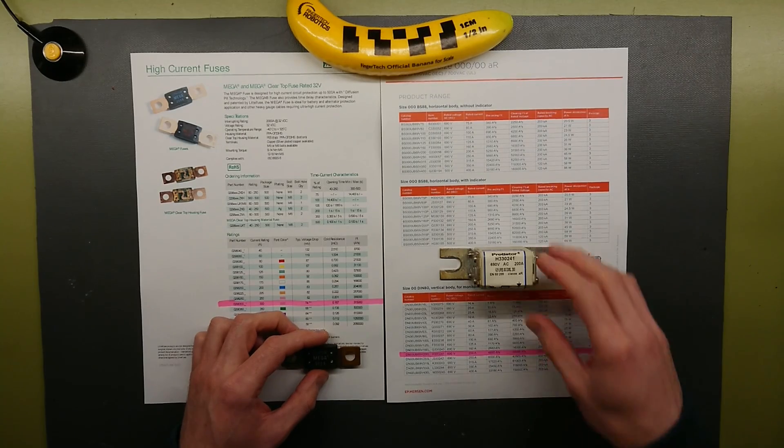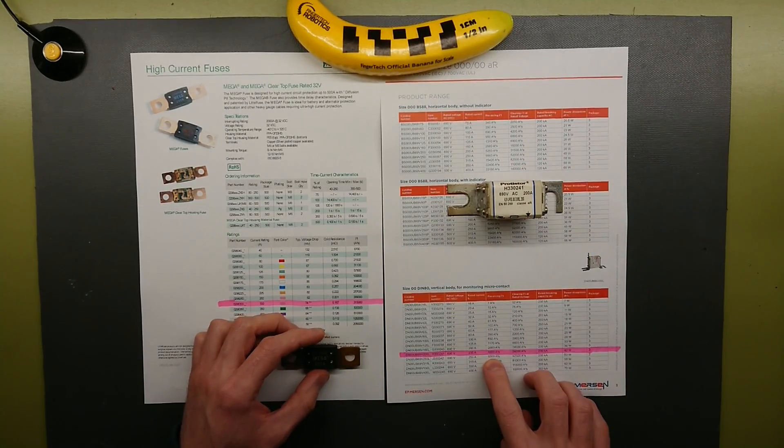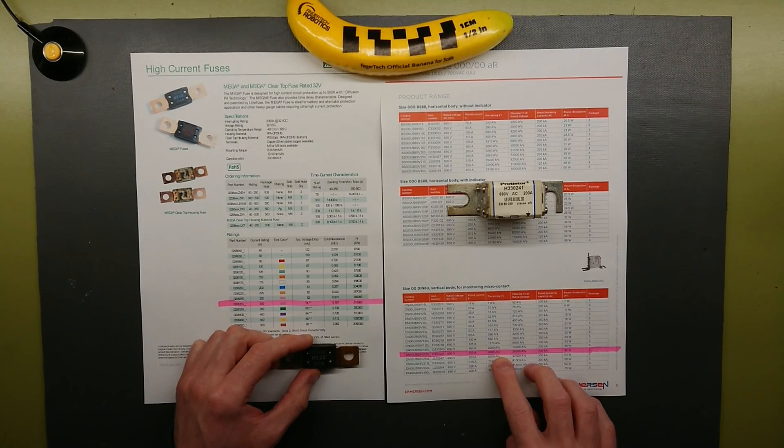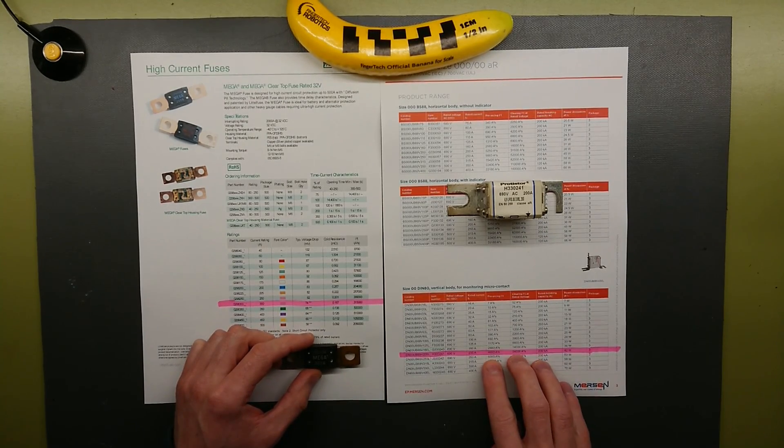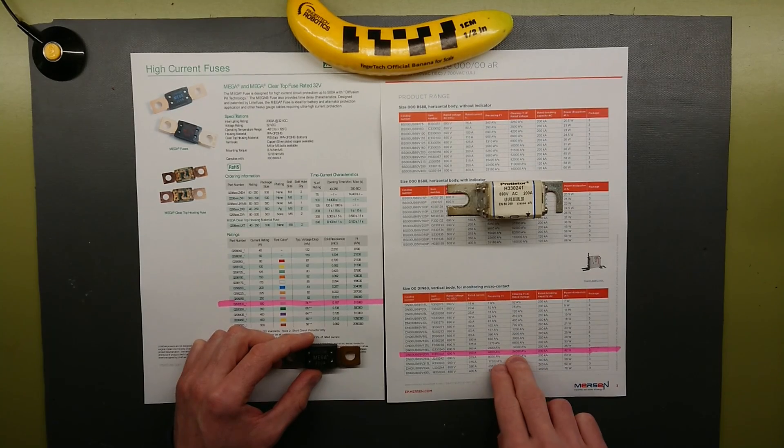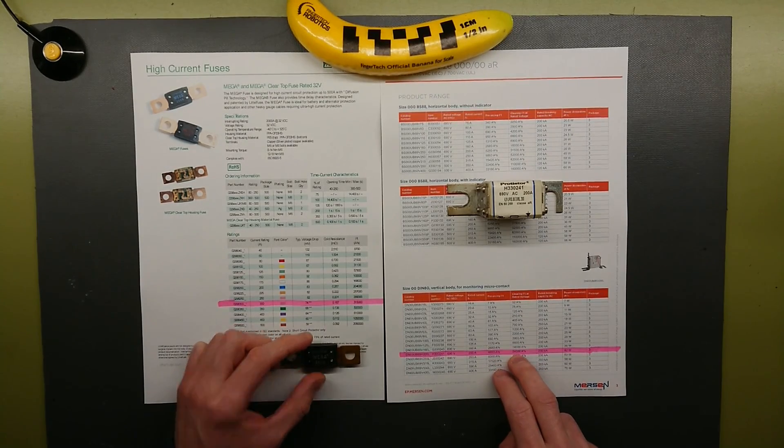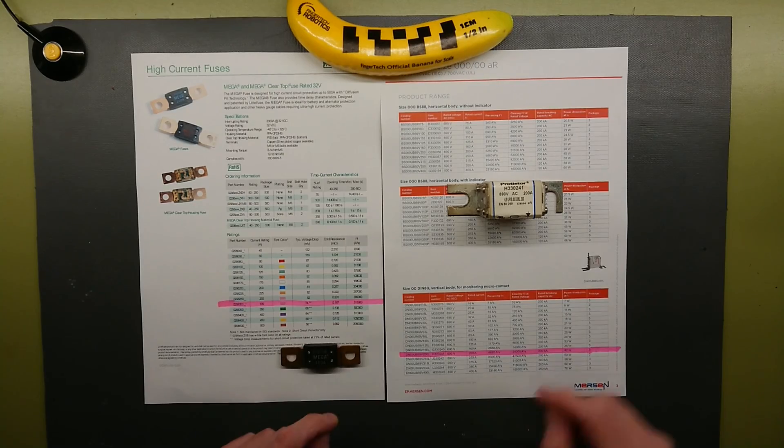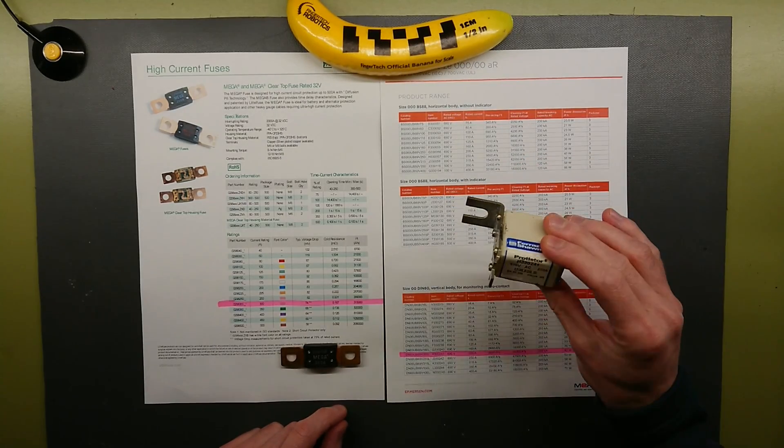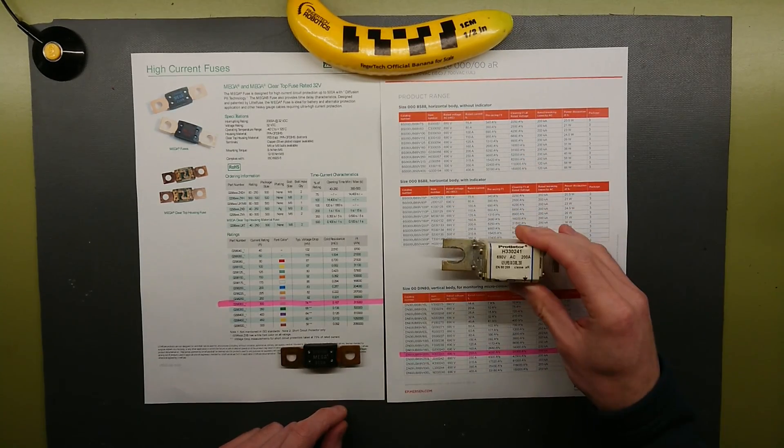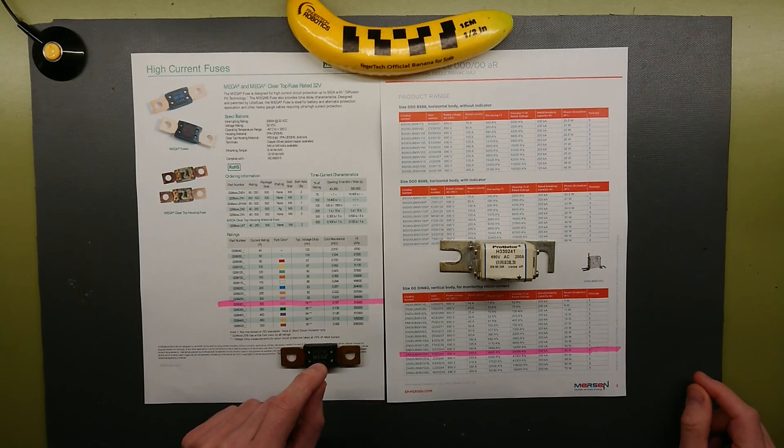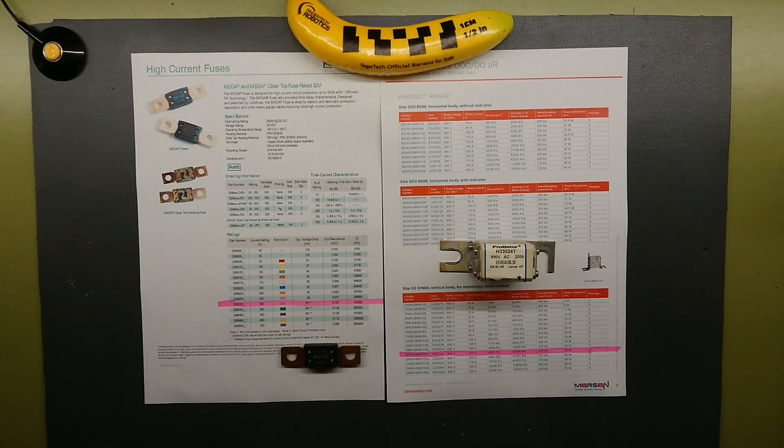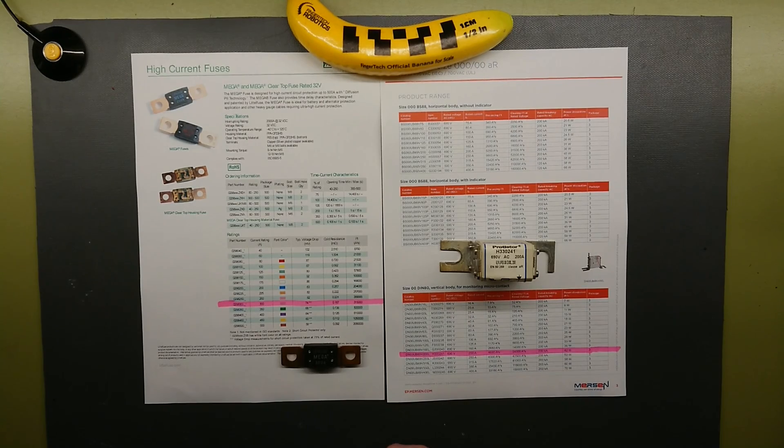If we look at the pre-arcing I2T, it's just shy of 5000 ampere squared seconds. It has a clearing I2T at 24,000 while it has over 300,000. So this is actually a fast acting fuse, while this is a time delayed fuse. Let's get them taken apart and find out what the difference is.